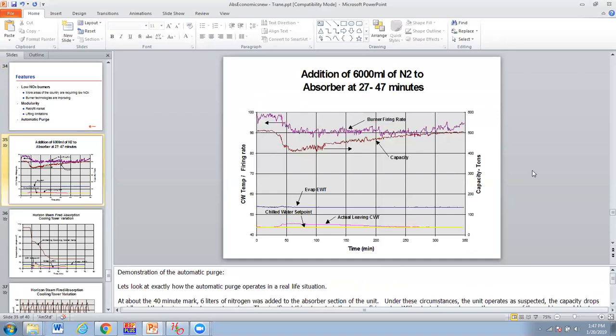So now we have a number of printouts. This must be from a real unit. That's just not a simulation. So let's take a look at this. What they've done is give the chiller some sort of difficult change of one of the inputs, and then they look and see how the automatic controls respond to it. So this one, they injected a bunch of nitrogen into the absorber.